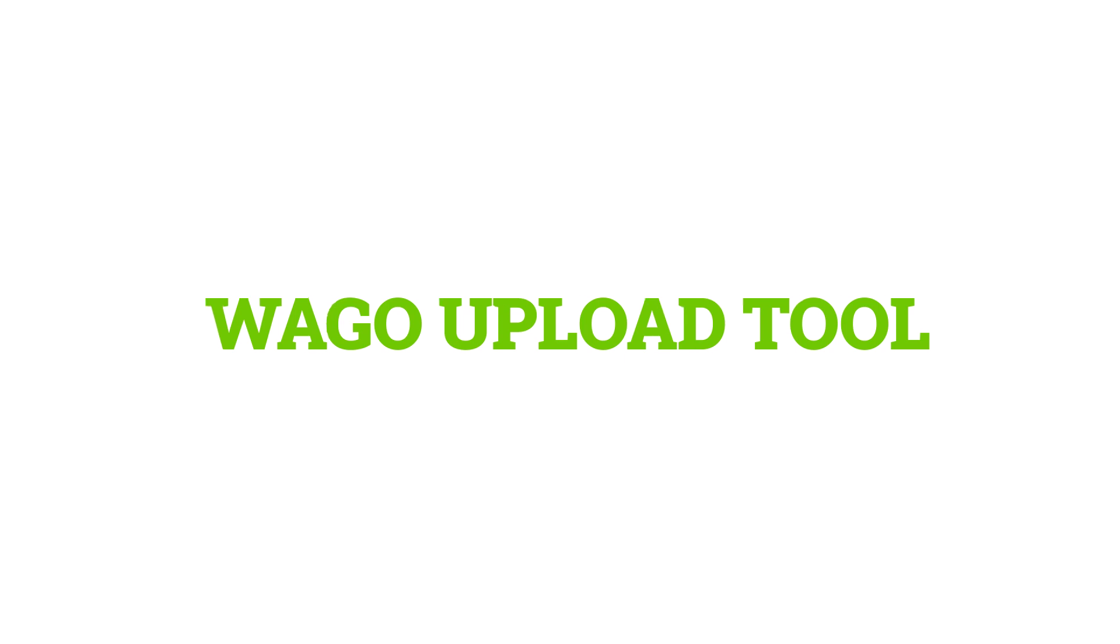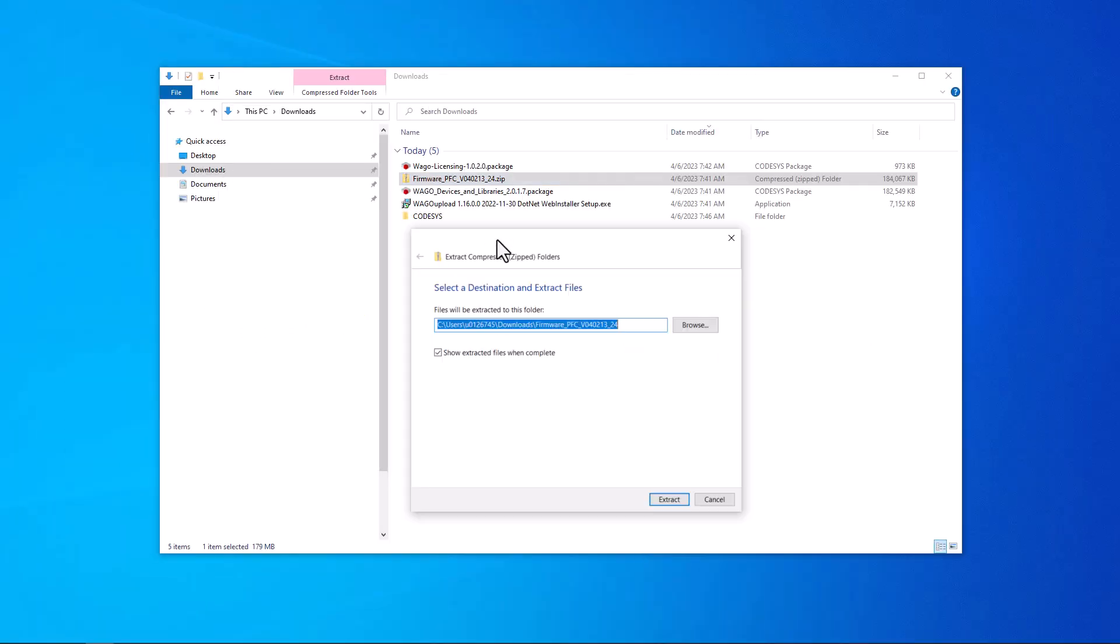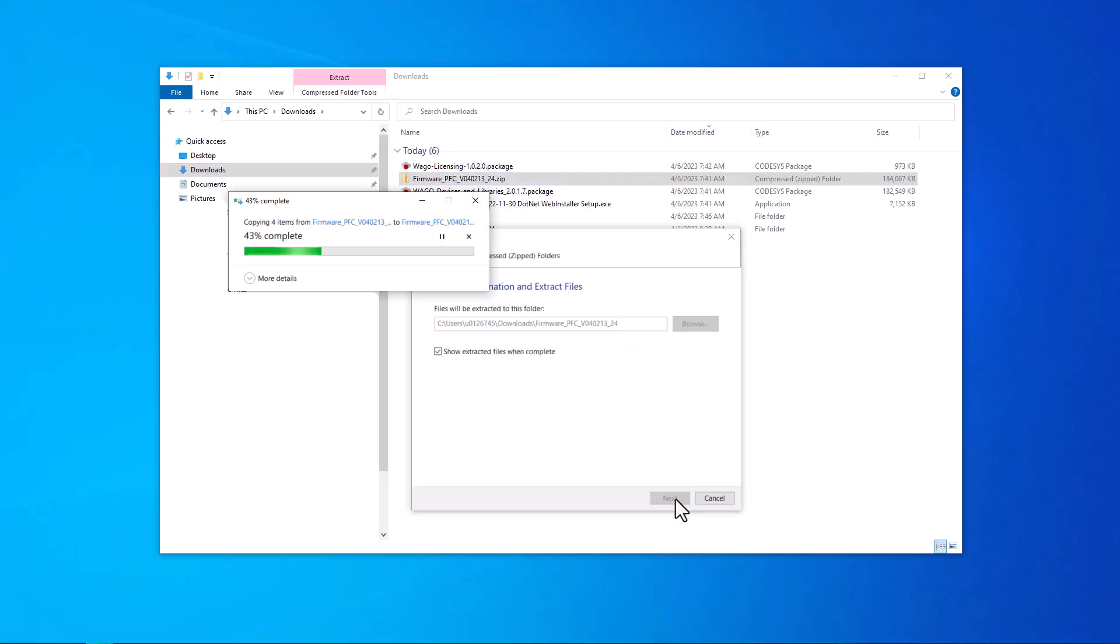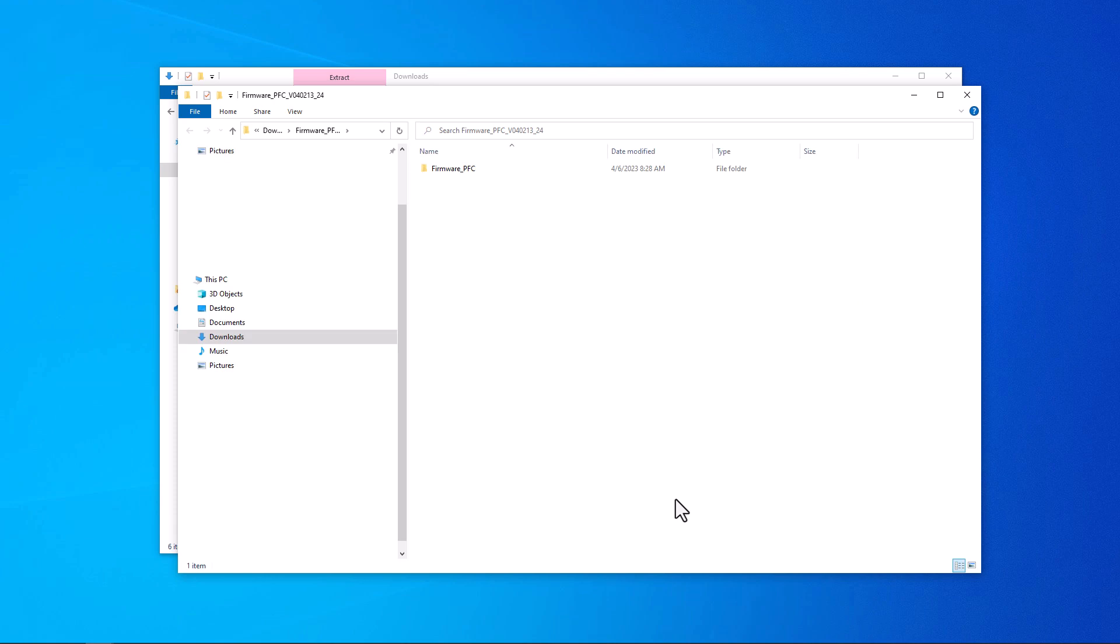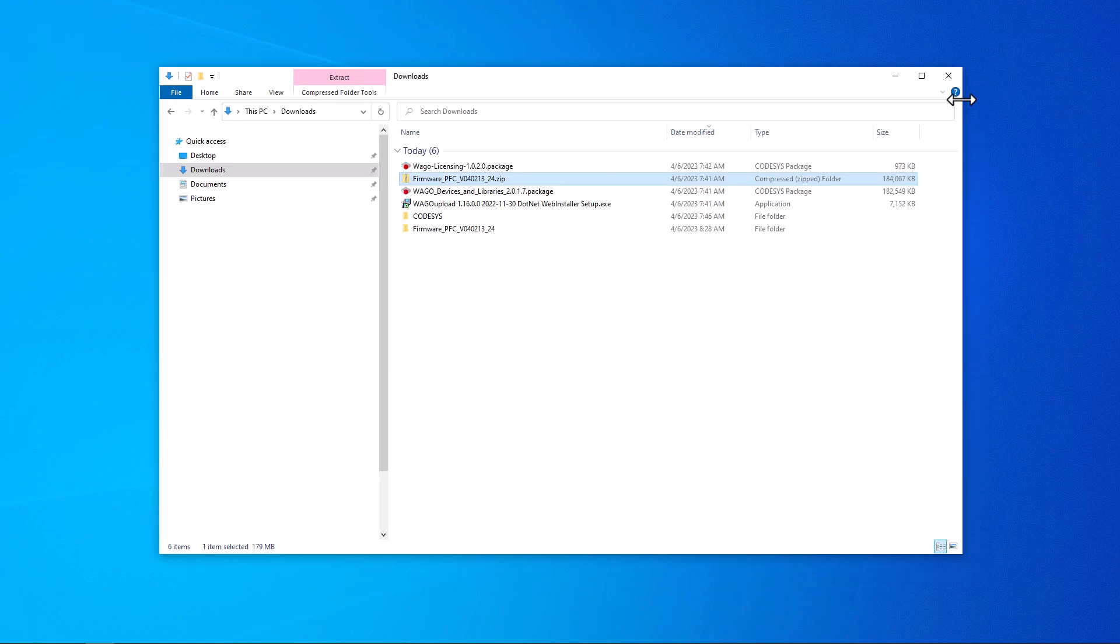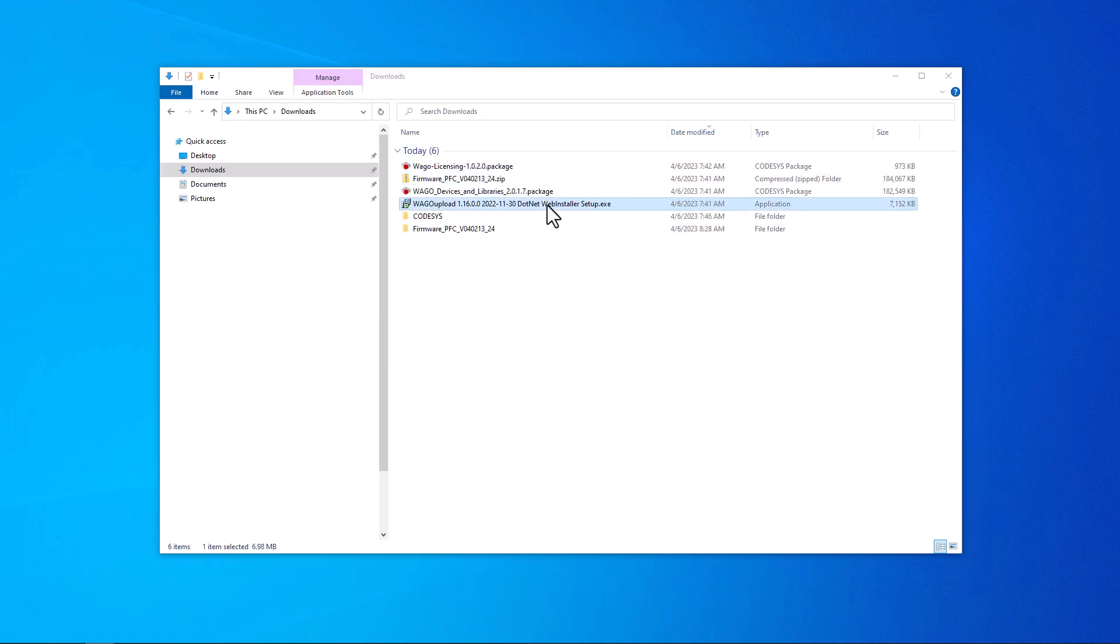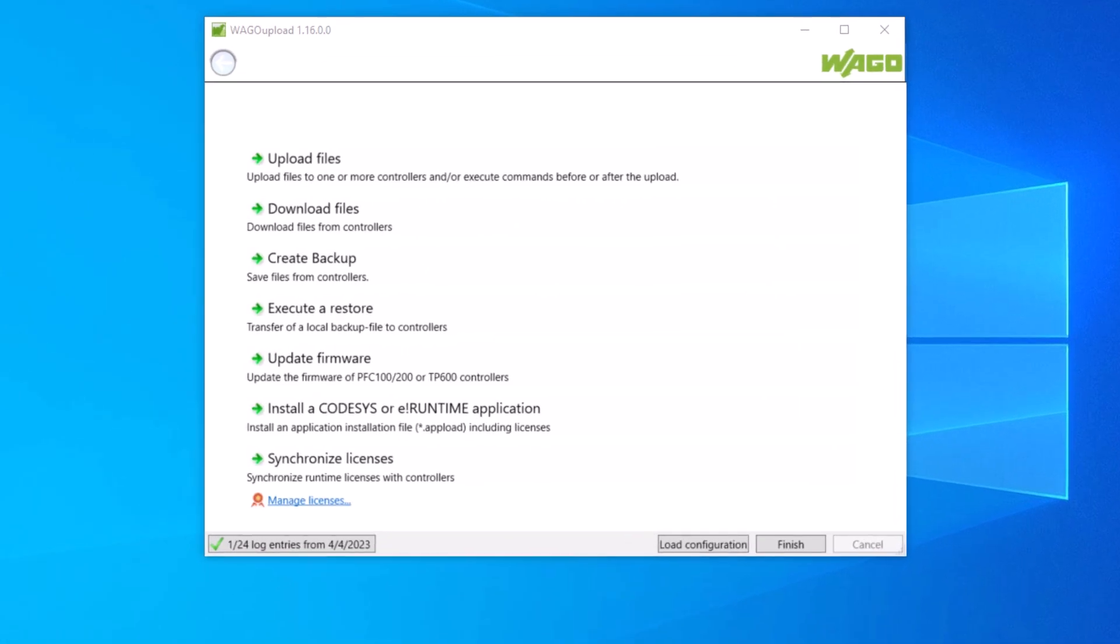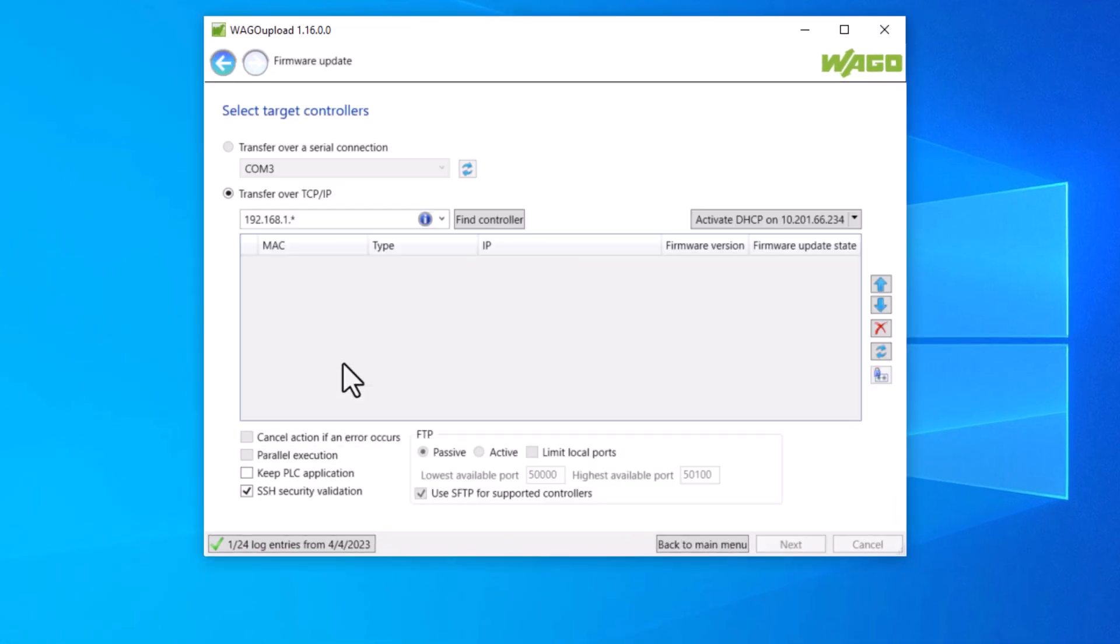Now we want to install firmware 24 on the PFC. At first we have to extract the downloaded firmware zip file. Then we open the downloaded exe file WAGO upload. The WAGO upload tool opens. Then we select update firmware and the firmware update window opens.